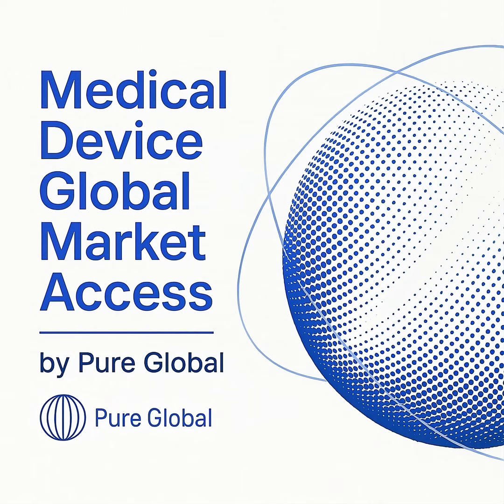So, what exactly are these obligations? There are three core components to the TGA's UDI requirements. First, manufacturers must assign a UDI to their device and all higher levels of packaging. This UDI must be obtained from a TGA-recognized UDI issuing agency, such as GS1. Second, a UDI carrier, which is a machine-readable format, like a barcode or QR code, must be placed on the device label and its packaging. This allows for the electronic capture of device information throughout the supply chain.